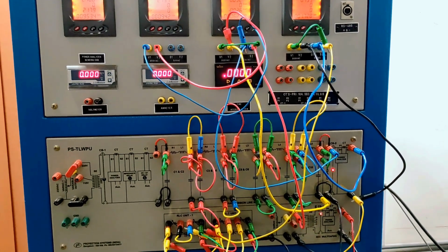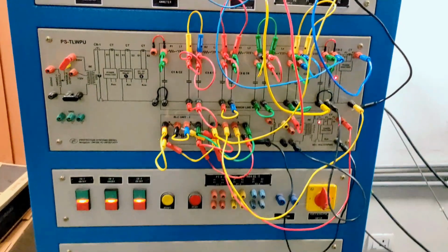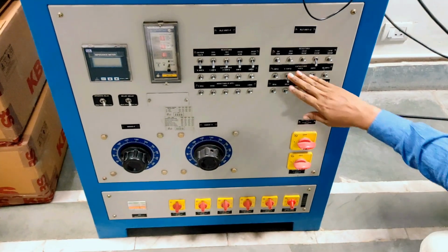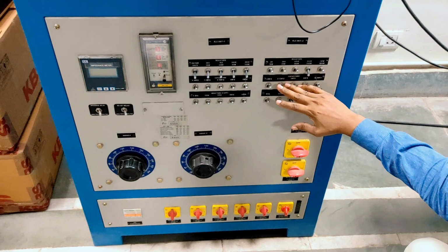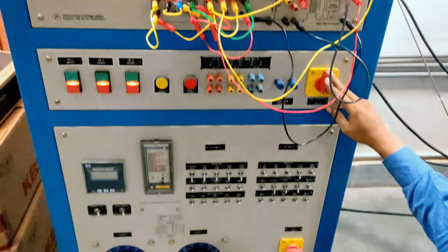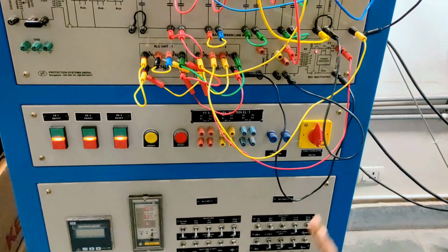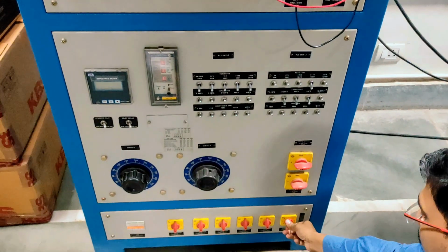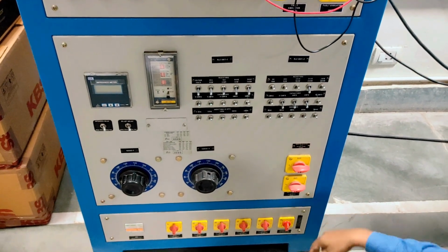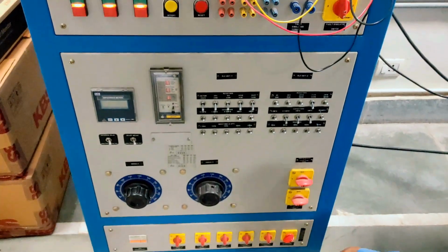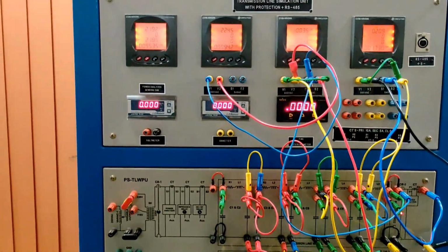Similarly, let's see what the tap changing benefits are. Our voltage is already adjusted at 0 voltage regulation, 220 right now, and the output, or the secondary side, of the tap changing transformer is connected to the C load. If I increase the tap changing position from 1 to 8, what will happen? Our voltage will increase. You see I am changing the position from 1 to 2, and our voltage has increased to 224.